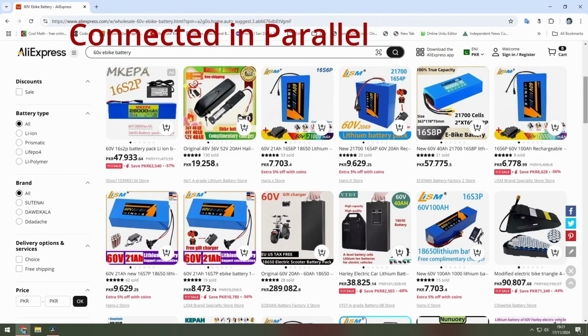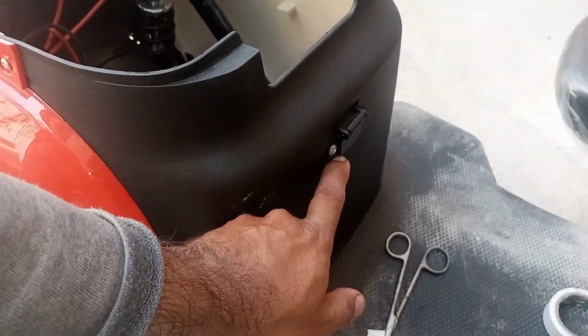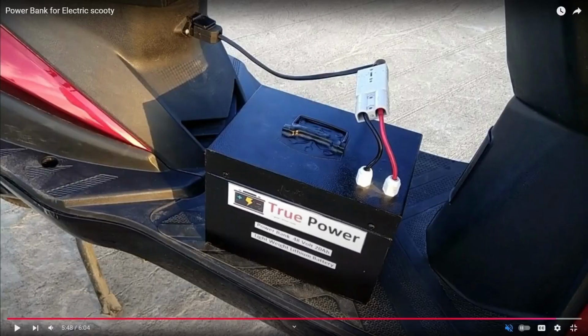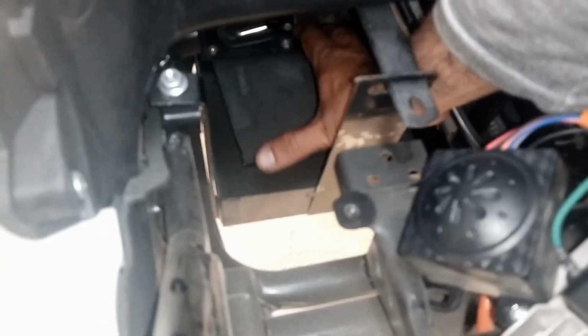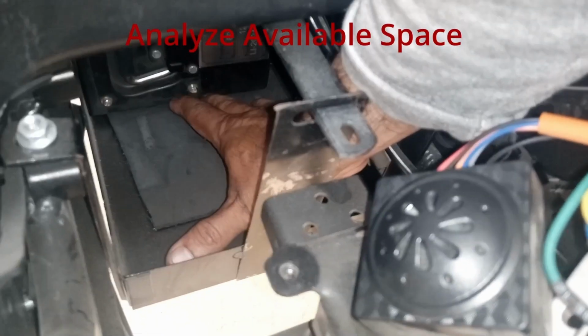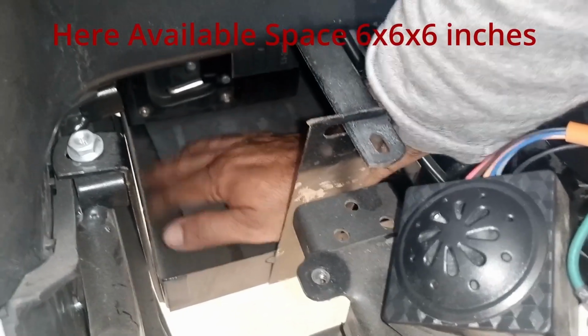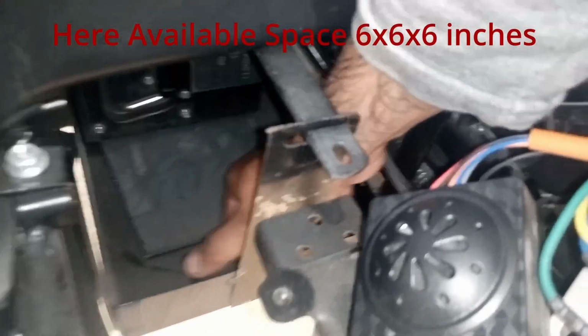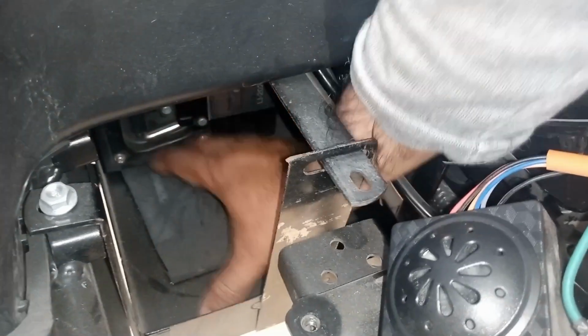Potential issues. Imbalance risk. Unequal charge levels can lead to one battery overcompensating, causing faster degradation. Simultaneous degradation. Both batteries will degrade at the same rate, even if the backup isn't always needed. Safety concerns. Without careful monitoring, the batteries could overheat due to mismatched BMS operations.